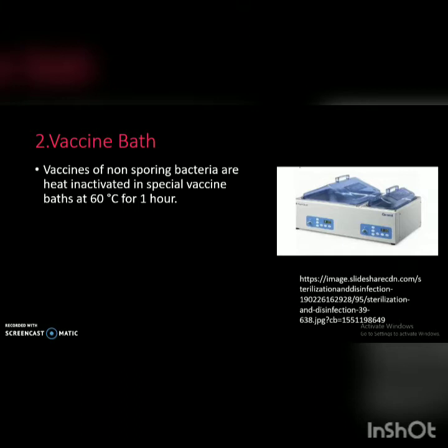Second one is vaccine bath. It is mainly used for the sterilization of vaccines. The vaccines of non-sporing bacteria are heat inactivated in special vaccine baths at 60 degrees Celsius for 1 hour.